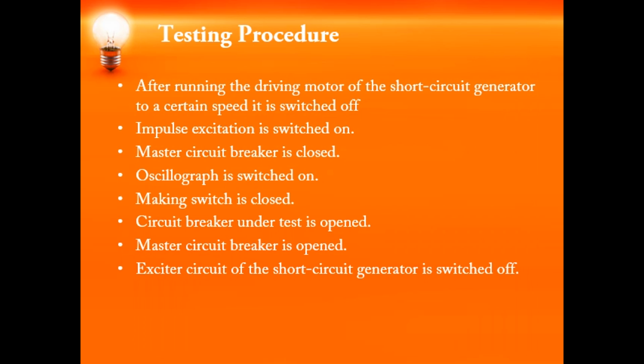So this is the procedure. The testing procedure is given here. This is how the laboratory type testing is done. It has steps, one by one, and the same way it has to be carried out. Usually this testing is not possible to perform manually, so you have an automatic control for this purpose. Usually the time of operation of this particular testing is 0.2 seconds.